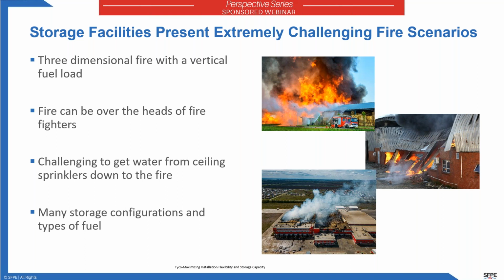Storage facilities get a whole bunch of chapters now in the NFPA 13 document. In fact, if you're now familiar with the NFPA 13 2019 edition, you're aware that the storage chapters have been completely rearranged. Previously, prior to 2019, NFPA 13 showed the storage applications based on both the type of storage arrangement and the type of commodity being protected. In 2019, there was a significant change made where now the storage applications are broken down by the type of sprinkler. So there's a chapter for the CMDA applications, there's a chapter for control mode specific application, or CMSA sprinklers, and there's a chapter on ESFR, early suppression fast response sprinklers. And I'll get into that in a little more detail.